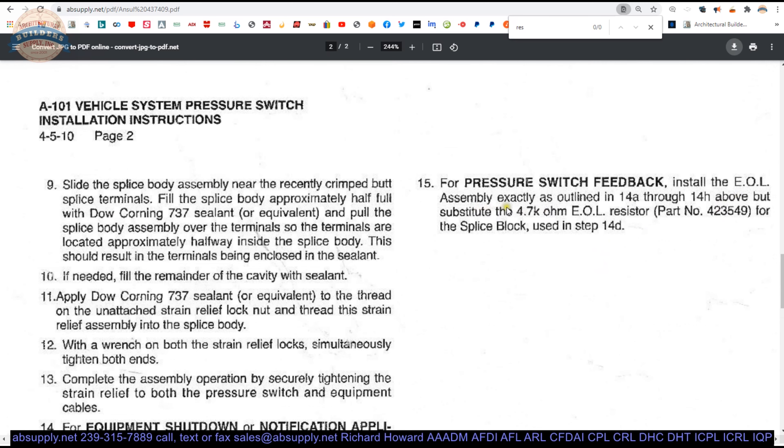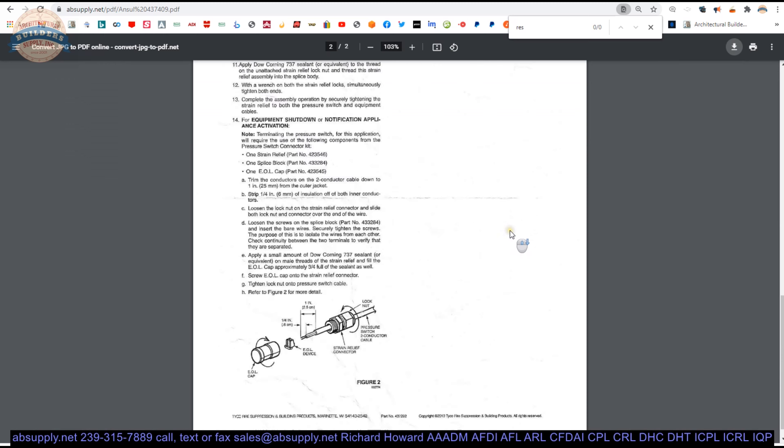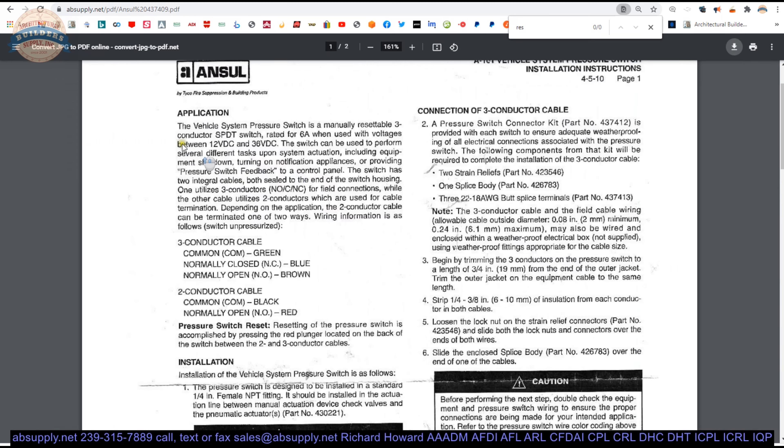For pressure switch feedback, install the EOL assembly as outlined in 14A through H, right through this section here. But substitute the 4.7 kiloohm EOL resistor for the splice block used in 14D. So if you're doing pressure switch feedback, you'll use that resistor.